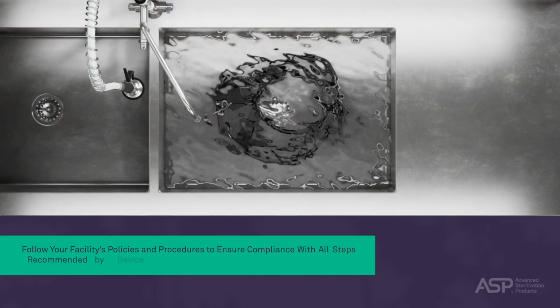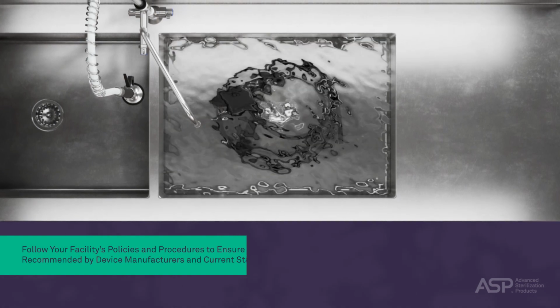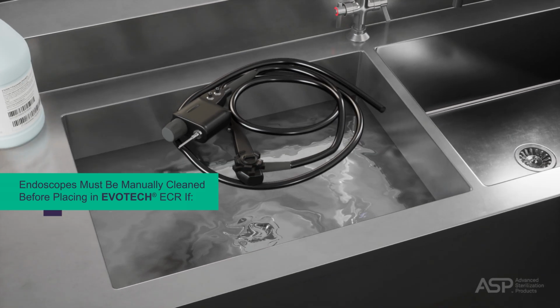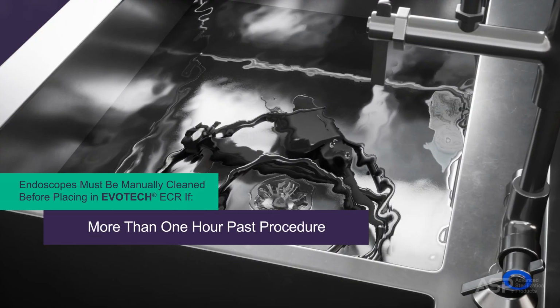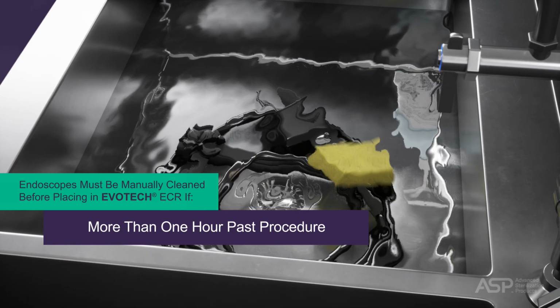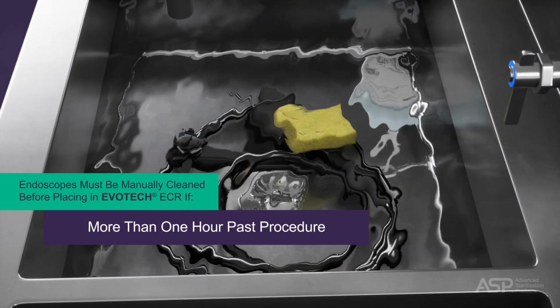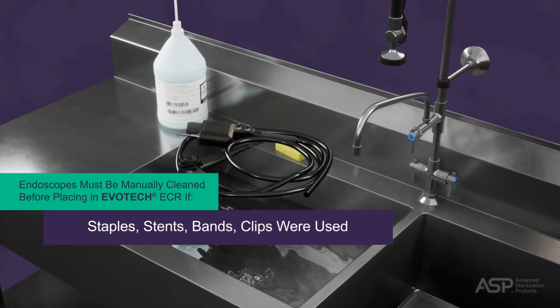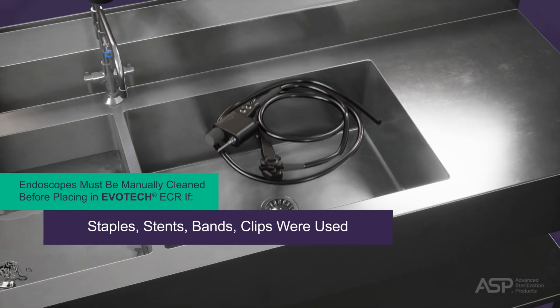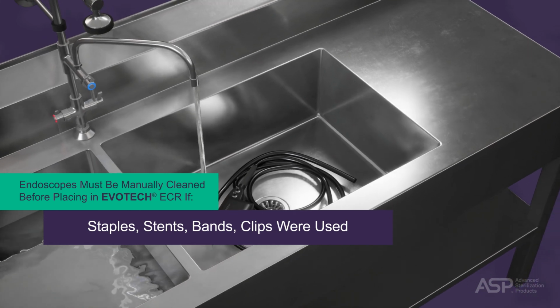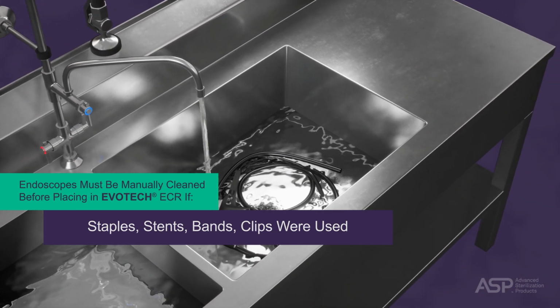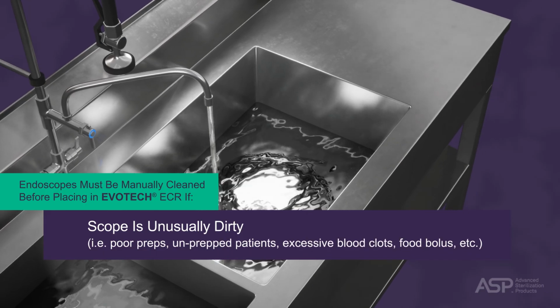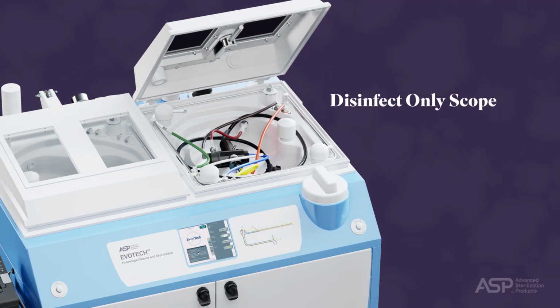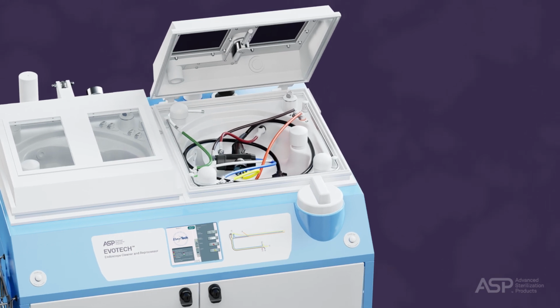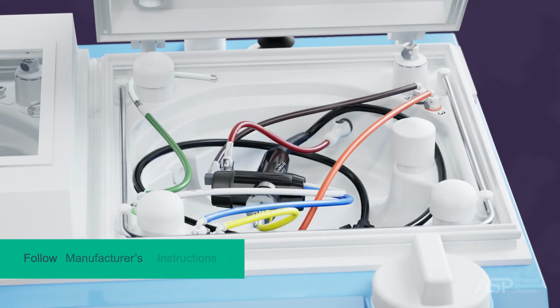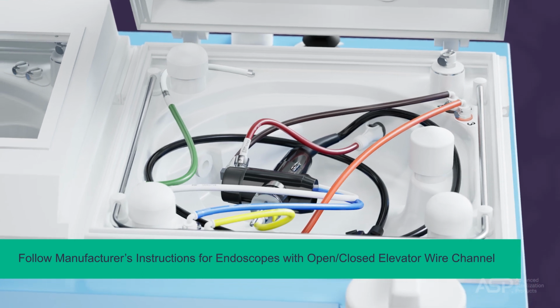There are times that we require you to manually clean a flexible endoscope prior to placing in the EVOTECH ECR. These are: if the endoscope sits for greater than 1 hour from the time the endoscope is removed from the patient until it is placed in the EVOTECH ECR; if utilizing bands, clips, stents, or any inorganic material during a procedure, check the channels to make sure they are not in the channels as they may become lodged; if the case was an unusually dirty case; if the endoscope is a disinfect-only scope; if it is an endoscope with an open-closed elevator wire channel, strictly follow manufacturer's instructions for manual cleaning.